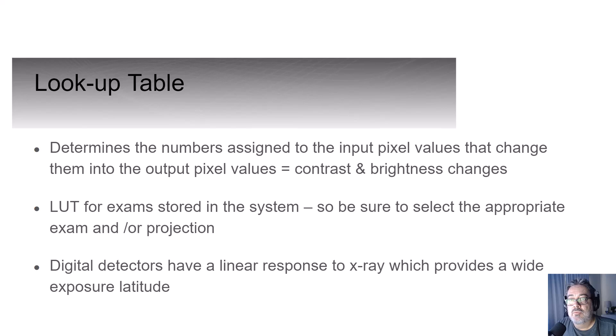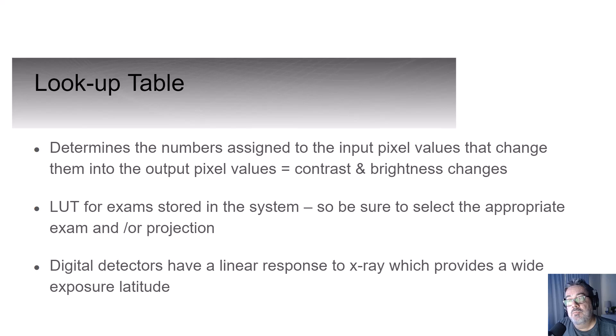A lookup table is essentially an algorithm or predetermined set of instructions that the software applies to the initial image histogram in order to present a very specific type of appearance on the radiograph. If you select PA chest when you perform that view, the computer will assign the lookup table to make that image appear optimum once it receives the data from the actual radiograph produced.